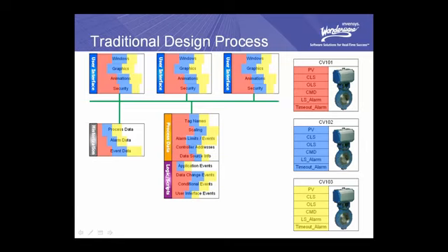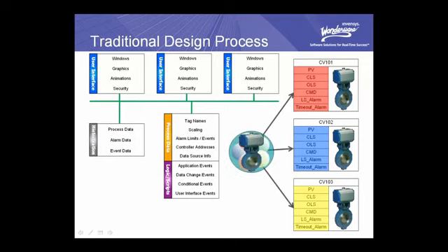What Application Server enables you to do is separate the components that don't belong together and combine the ones that do. You see, with Application Server, you define a template that contains all this information, all the data points associated with the device, all the logic and scripting related to the device, all the alarms and limits, what should be stored in the historian, and even what graphics are associated with the device. All these things are contained within a template definition.